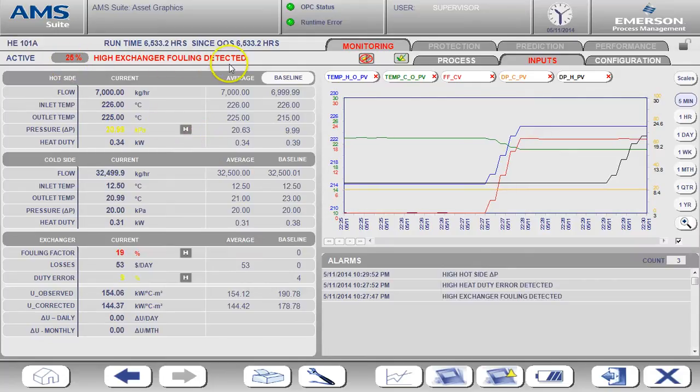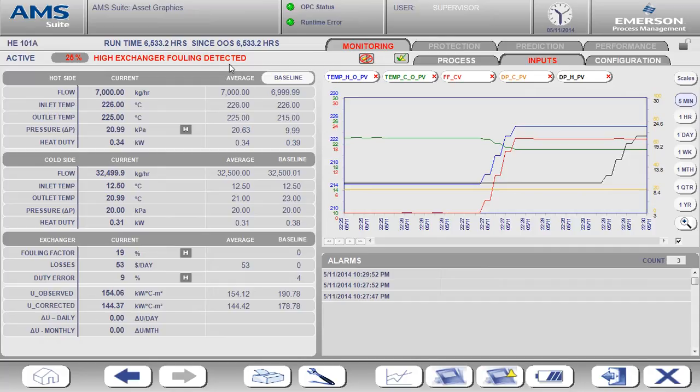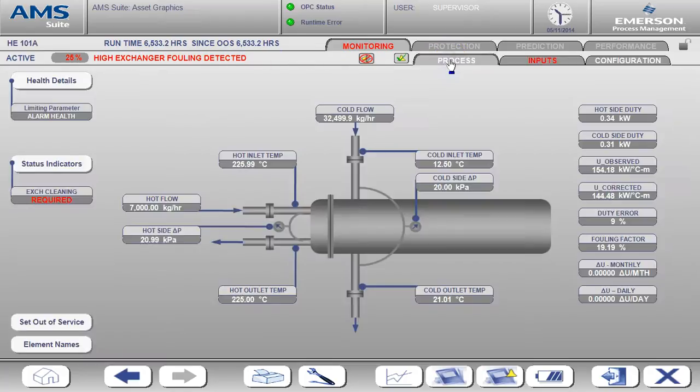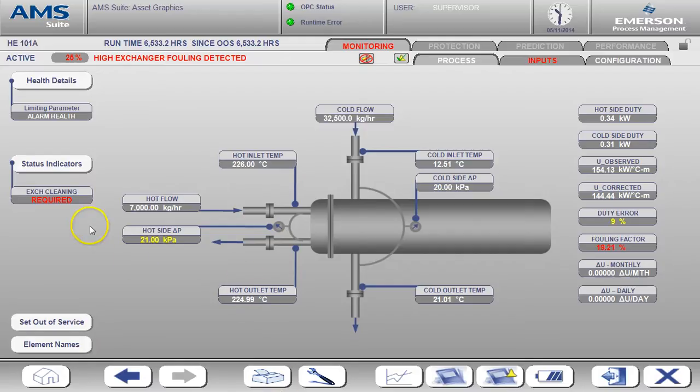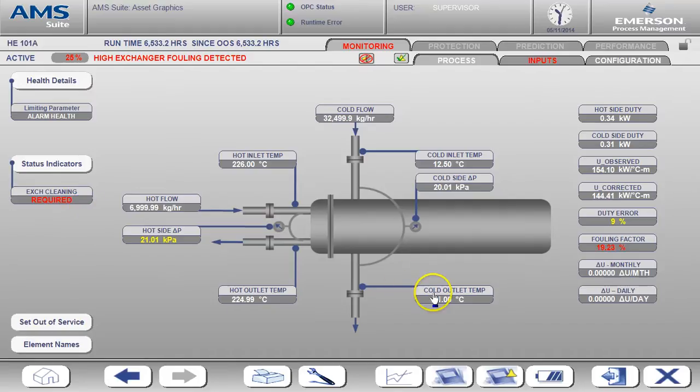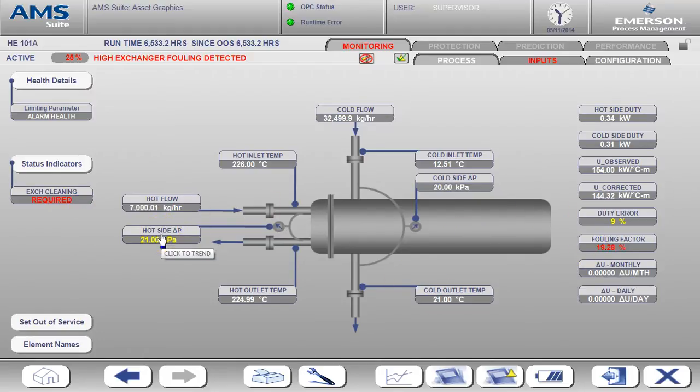But let's go back to the process page and look at the exchanger cleaning status. Now we see that the exchanger cleaning is set to required. Not only do we have a high fouling factor, but we also have a high differential pressure on the hot side. This indicates that it's time to clean the exchanger.